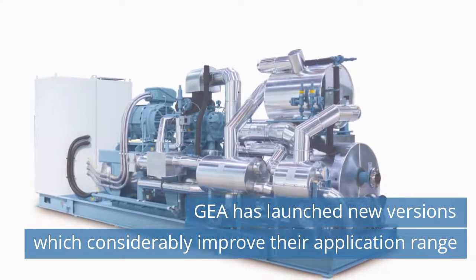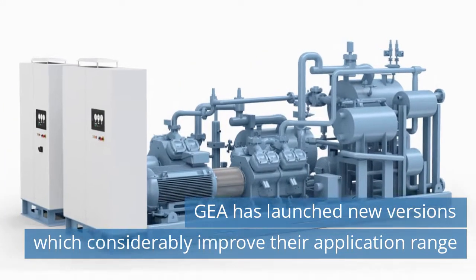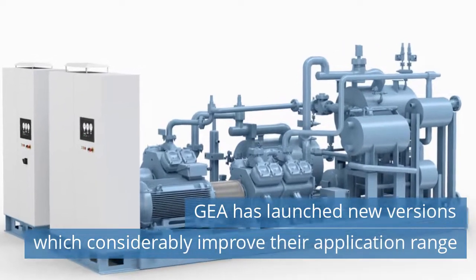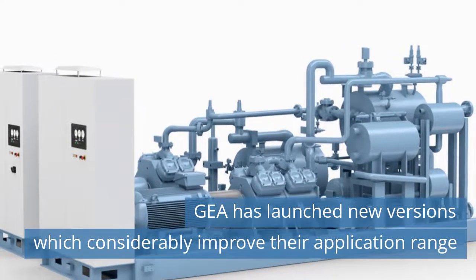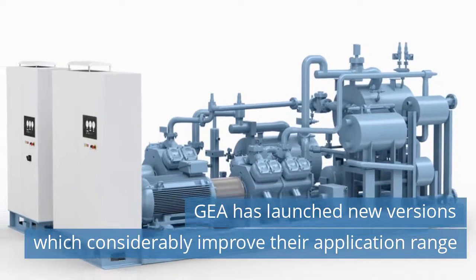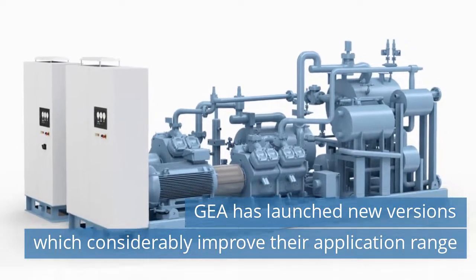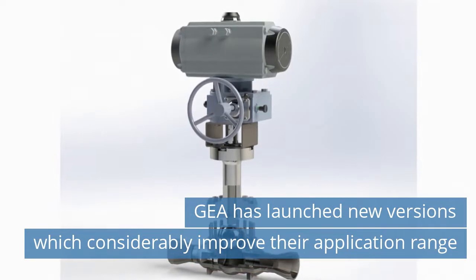The new GEA Red heat pump cascade version allows clients to add the heat pump onto any existing refrigeration system, while using one single ammonia cascade heat exchanger that works as the condenser for the chiller stage and as the evaporator for the heat pump stage.